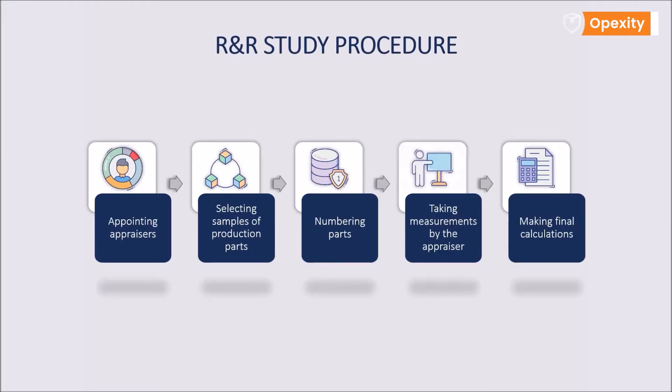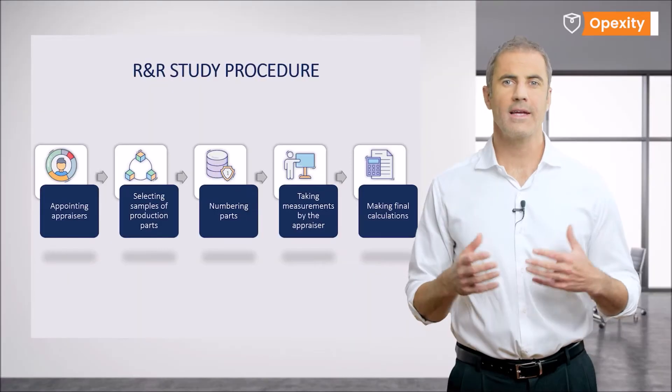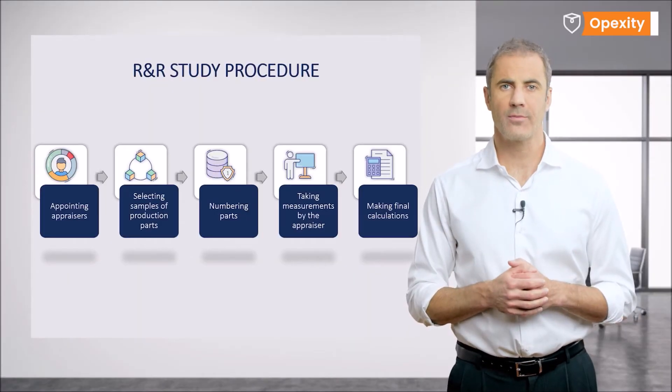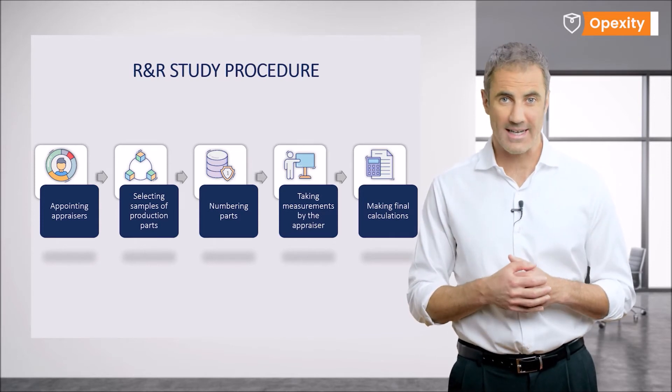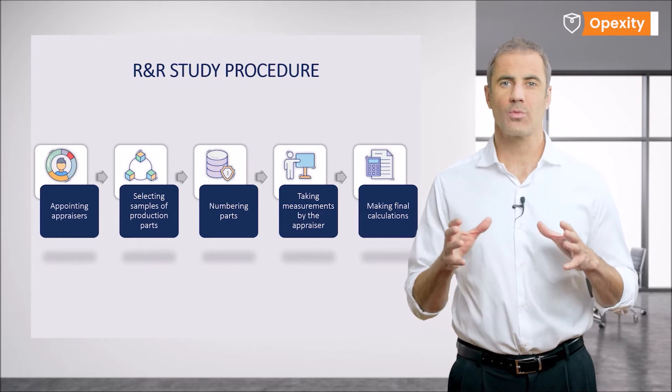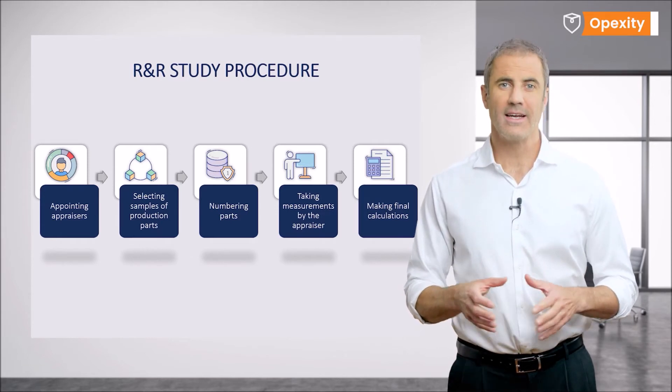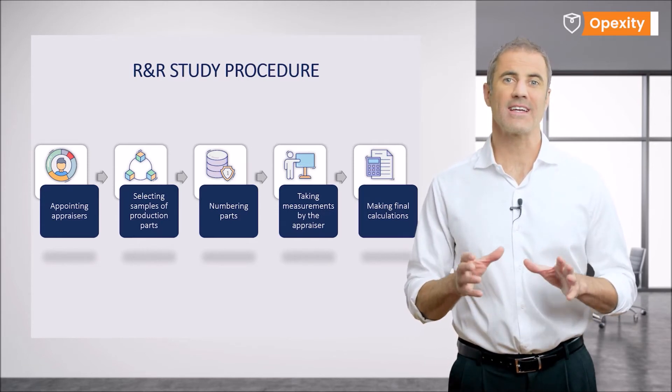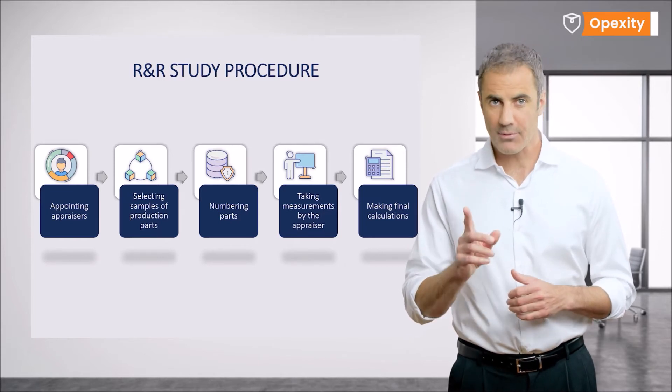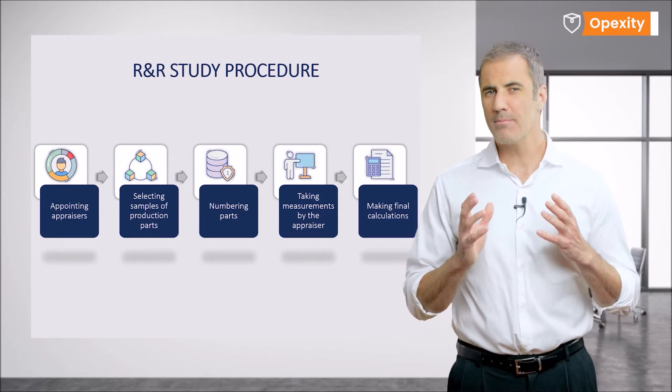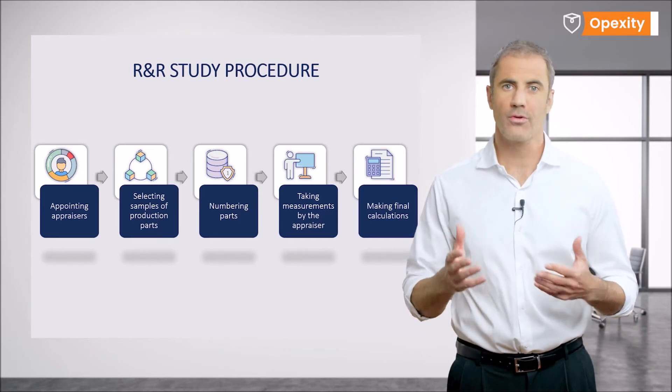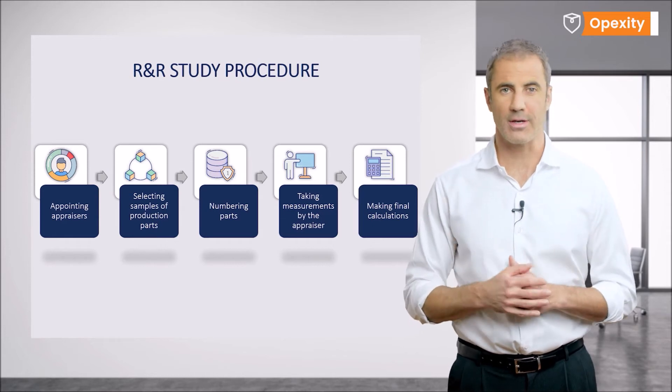Then, in taking the measurements, the process is carried out under the supervision of the study leader. In order to ensure that we account for the variability of the measurement that results from its way of performance and the method selected, we can't take just one measurement. It is usually recommended to conduct at least two tests for each piece, separately by each appraiser. In most cases, there are two, three or four tests conducted, usually three.